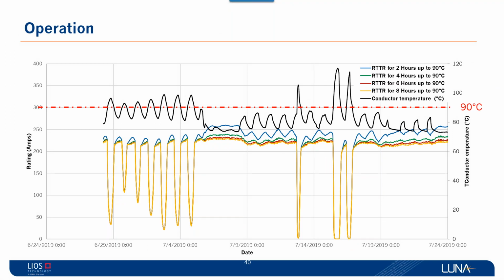90 degrees Celsius is the limit. At the same time, 250 amp. So when they're operating, they can see that I can never operate this line for more than 2 hours. After 2 hours, I'm losing it. I'm losing my rating all the way to 0, 10 amp. I can only push 10 amp. And they can see that every time they are overloading the line.